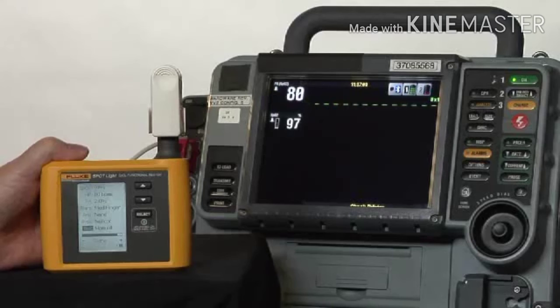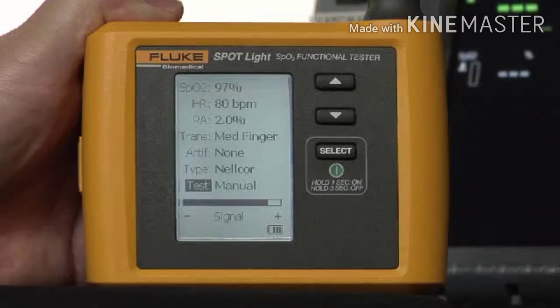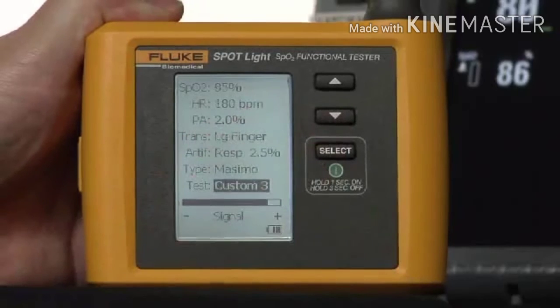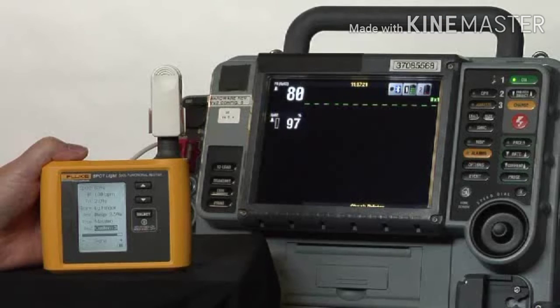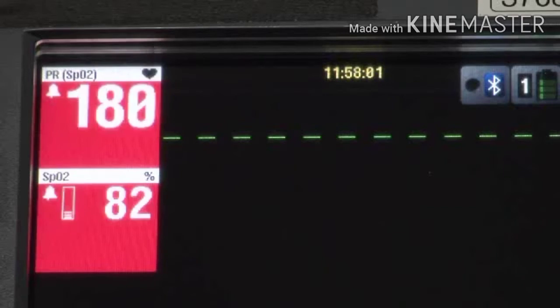Now, testing this functionally really quickly is just a 4-button push. We're going to go to our custom setup and go to custom 3, which is programmed for a patient with a high heart rate and a high O2 sat. You can see it sets off the high limit alarms, which is exactly what we want it to do. We'll watch till the oximeter reading and the heart rate settle.